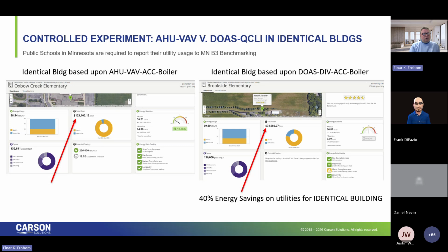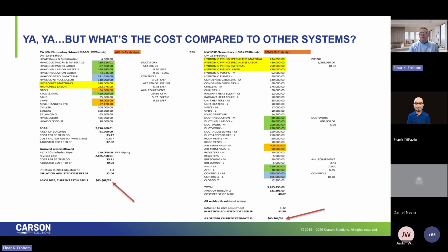So I asked the question, why wouldn't we do this? I apologize for the font and the array of information on the slide, but that question was put to one of my favorite repeat offender engineers, and the GC said, you're going to blow the budget by $800 to $1 million with this DOAS and displacement induction ventilation thing. And that engineer took it upon himself to prove him otherwise. He looked at a school that he designed with air handler VAV, captured all the live bid data, all the labor rates, all the piping costs, ducting cost, controls cost, and he boiled it down, inflation, labor rates, to about $52 a square foot.